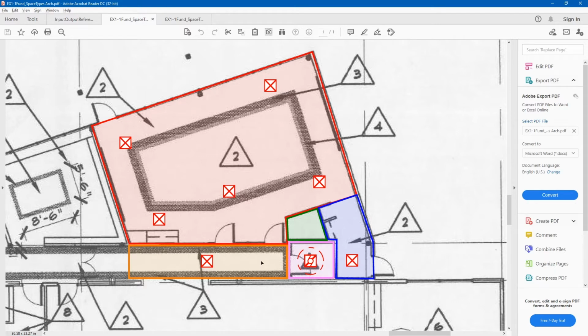and it's totaling up all of those lighting loads, and it's assigning it to that single thermal zone so that EnergyPlus can run it. And it does the same thing for people loads, and it does the same thing for equipment loads, and all of those values, outside air loads or ventilation loads, all of these get totaled up and passed to EnergyPlus, and EnergyPlus runs this as a single room with the combined characteristics.